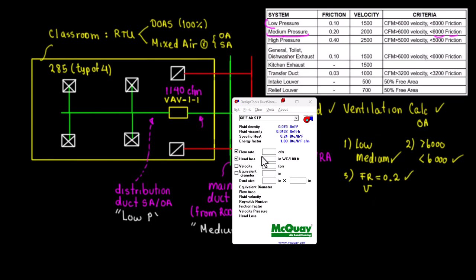In this case, let's put it in our online calculator. What's the CFM? 1140, and then the friction is 0.2. As you can see in here, it says 12.7. Let me put this in again. 1140, and this is 0.2. It says 12.7. Overall, most likely it's not going to go to 14, so this is diameter 12. That would be my inlet.